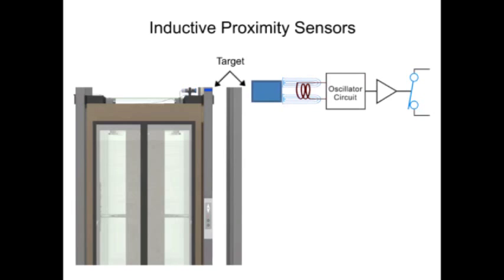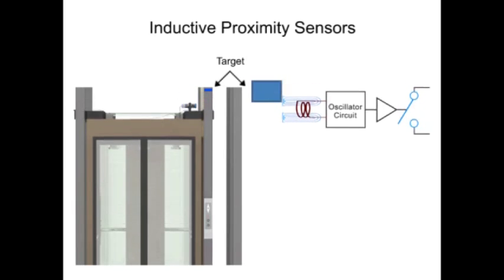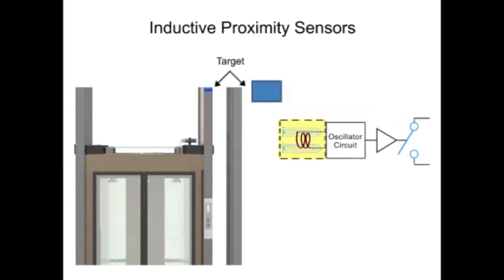This change in amplitude sends a signal to the switch, changing it to its normally open or normally closed configuration, respectively. When the metal target is removed from the sensor's range, the oscillator will return to its normal amplitude, and the switch will return to its normally open or closed output.